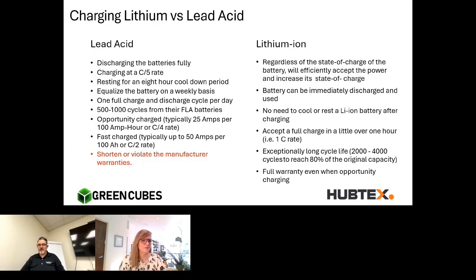A lot of people do a fast charge at about a C/2 rate, or a 2-hour time frame, but that almost always will shorten or violate the manufacturer warranty, and over time it will degrade the battery so you won't get its full warranted lifetime. So if a lead acid battery manufacturer tells you that you can fast charge it, always ask for the details of how that affects the cycle life of that battery.